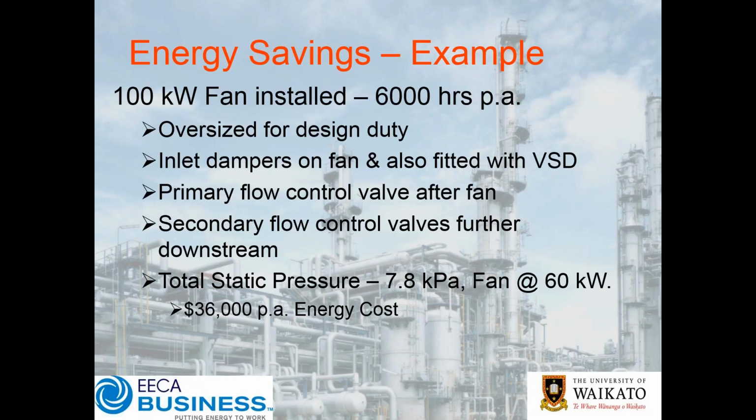Now, obviously, if you've compensated and had a rather large fan, we then take the approach, well, if we just put a bigger fan in and hook it up to a VSD, then no problem. We can just slow the fan down as we need to. Problem solved. Well, as we think about this, I want to share an example. It was actually a 110 kilowatt fan.